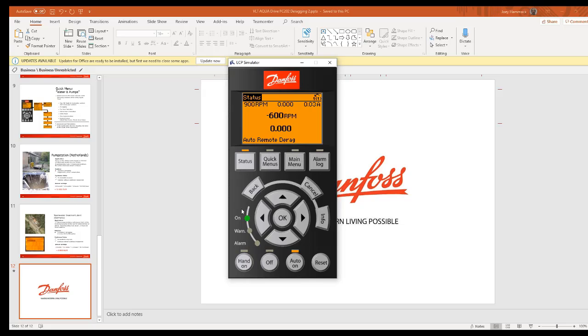Let me see my motor. The arrow changed. Is your motor running backwards? Hold on. Yes, it is. So it still worked. So that's something to note. The DERAG will override this, yes. So it did actually run backwards. So this didn't matter. Even if my controls are clockwise only, DERAG overrides that, and it ran the motor backwards. So note that. Yeah, that's great.